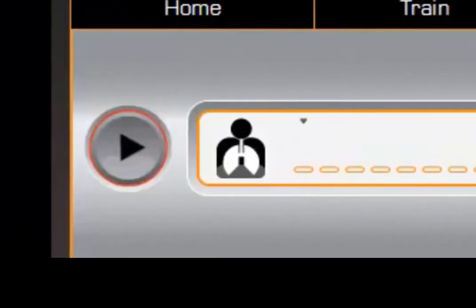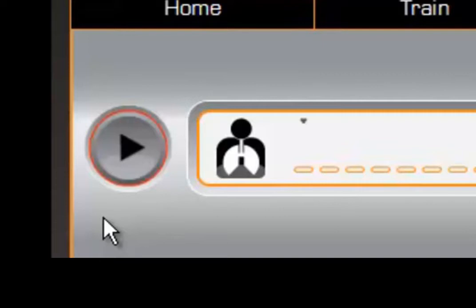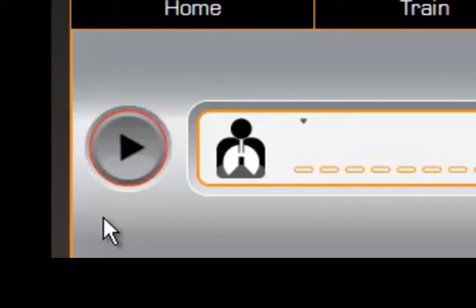Next to the information window is the start and stop button. To begin a test session, click on the start button and you will notice two things. Firstly, the PowerBreathe unit will calibrate the valve by moving it backwards and forwards and ending at the fully closed position. This indicates the beginning of a test session. Secondly, the start button will also change state to a stop button.